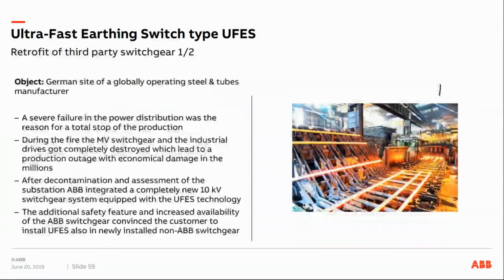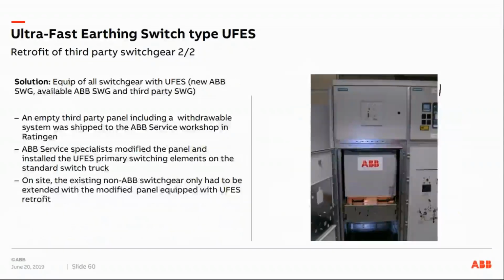Another application, heavy industries, a steel and tubes manufacturer. Here again, the customer was having an outage due to an arc fault, which ended up in monetary consequences for the customer. Here we found a solution to install ABB's truck solution, or UFES truck solution, in the customer's existing panel, as you can see here.